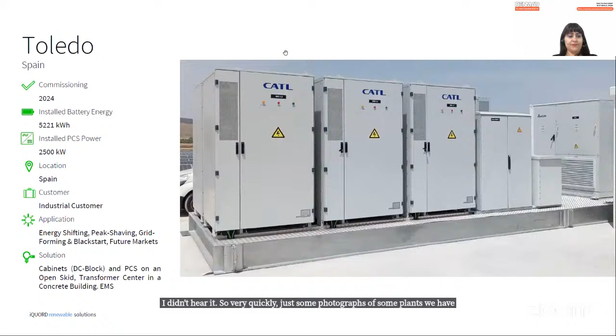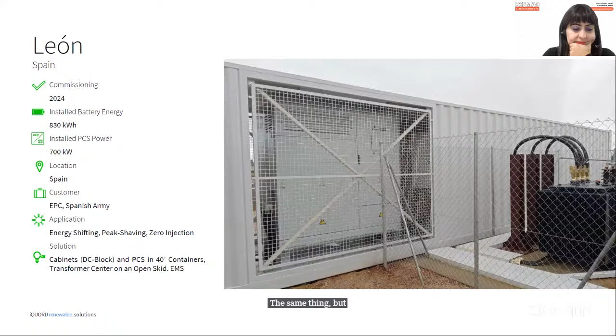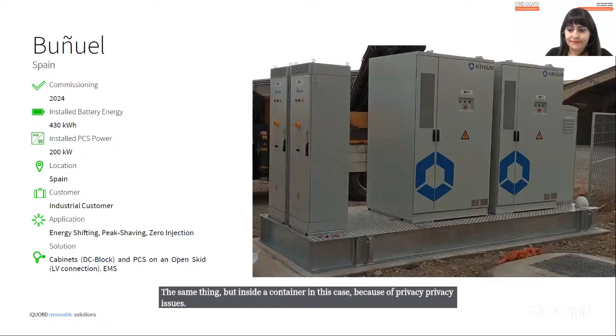Very quickly, some photographs of plants we have delivered with cabinets, central PCSs, the same thing but inside a container in this case because of privacy issues. Small ones with string PCSs, the same thing here. And then an e-house in which you can store up to 10 megawatt hours worth of batteries in a maximum 20 meters long and 5 meters wide e-house. This is mostly for big size plants, or can be used in a data center.